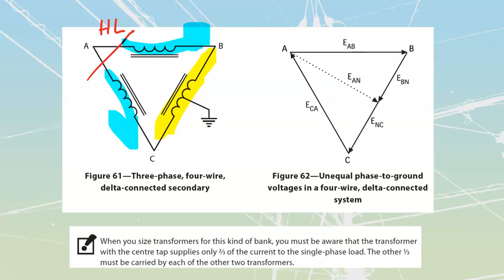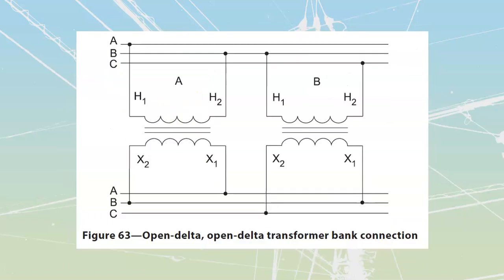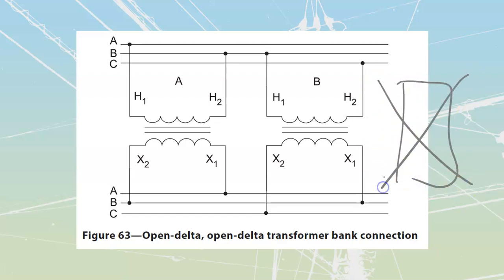The next one that you're going to see is what we refer to as our open delta transformer bank. An open delta transformer bank is where we just use two transformers on a three-phase system. So I have an existing three-phase system, and I only use two transformers to step that down. There are a couple of reasons that we might do this. We might do this just because it's a stopgap measure. You know, we might have had a bad failure on one of our transformers. Maybe there used to be a third transformer inside of here, but that third transformer is bad right now.